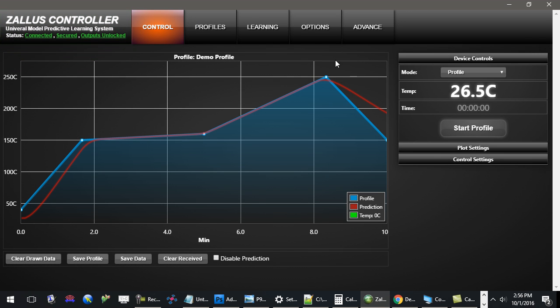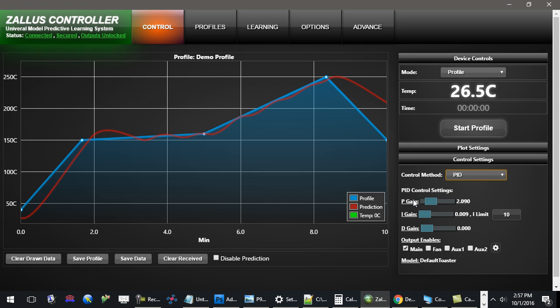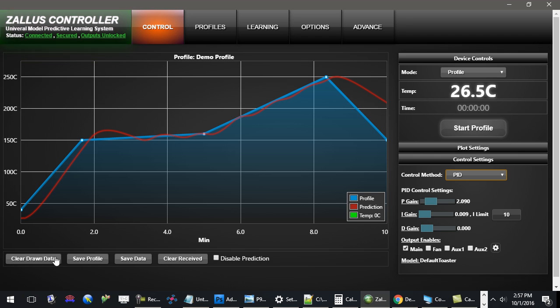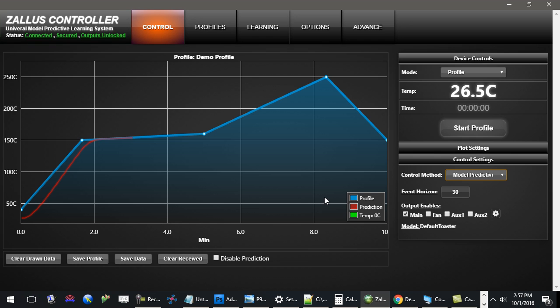The reason it tracks the system so well is because it uses model predictive control. Now many of you may have heard of a control method called PID control — PID stands for proportional integral derivative, and this control technology is over a hundred years old. It does not make use of the physics of the system, nor does it attempt to predict future needs and desires such that you meet a curve optimally. Because of the learning, it can allow you to tune the PID controller ahead of time, but no matter how you try to tune it, you will never be able to achieve this curve in the same way that model predictive control can.